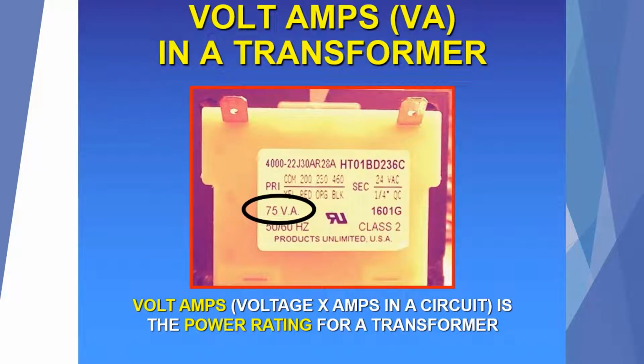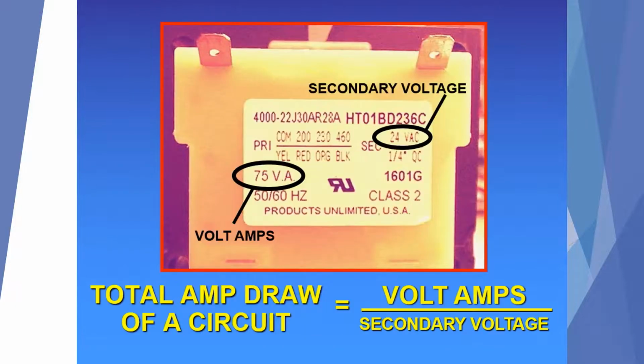Another thing that is very important to understand about a transformer in HVAC work is the VA rating of the transformer. This is the volt amps rating of the transformer. It is the power rating for the transformer and is the voltage that it can handle when you put a load on this transformer. What we can use the 75 VA rating for is to determine what the amp load is that this transformer can handle in a circuit.